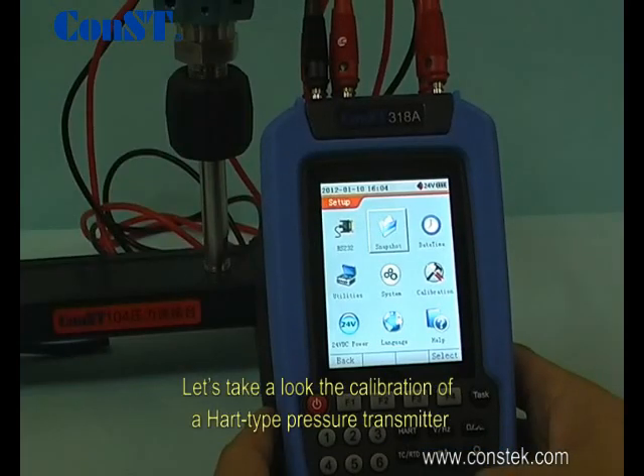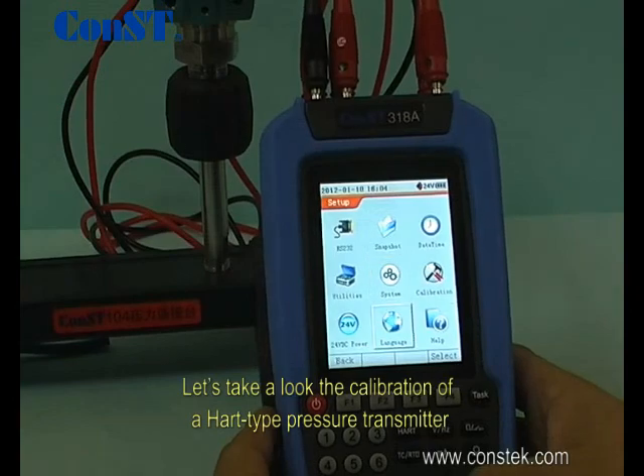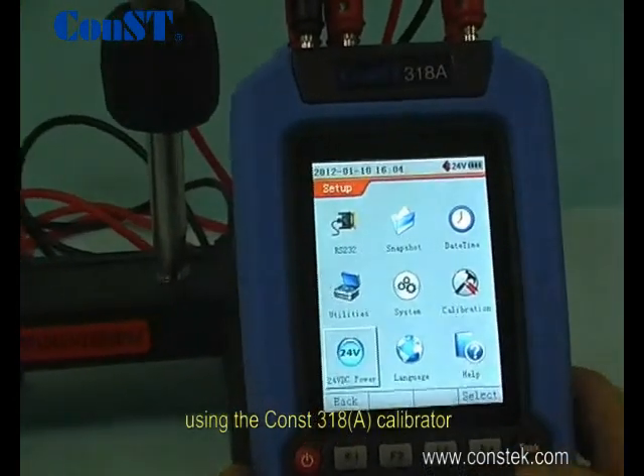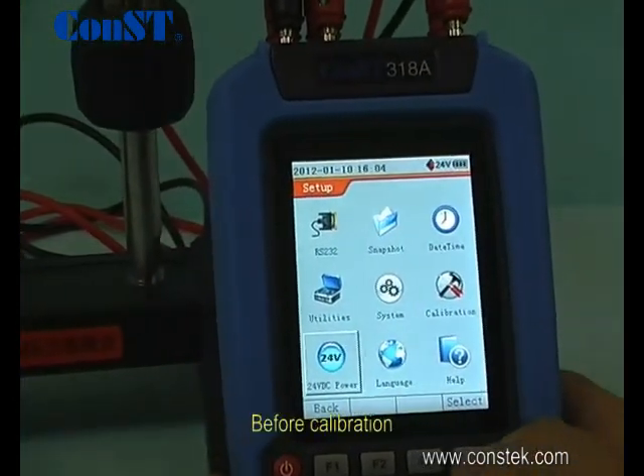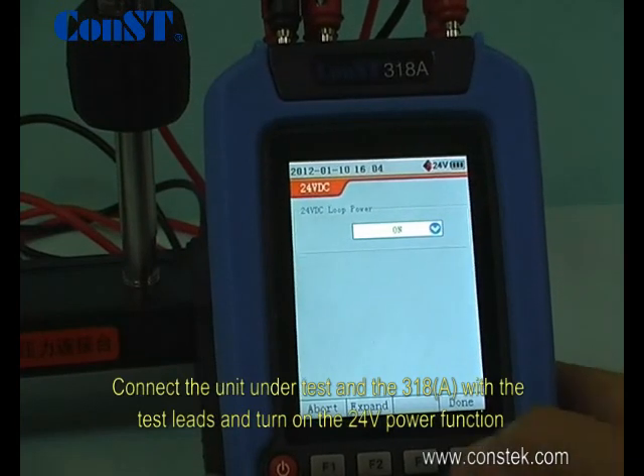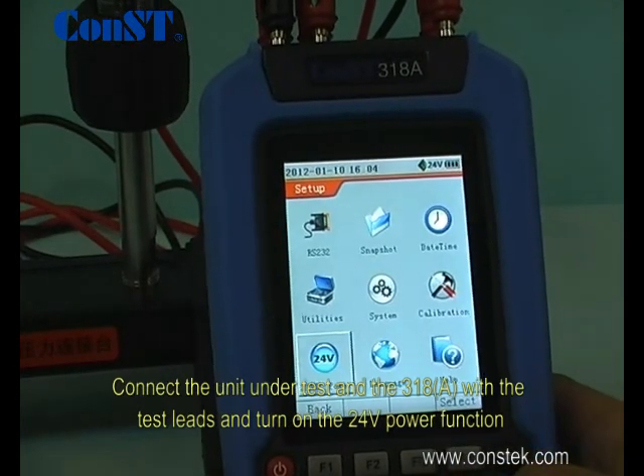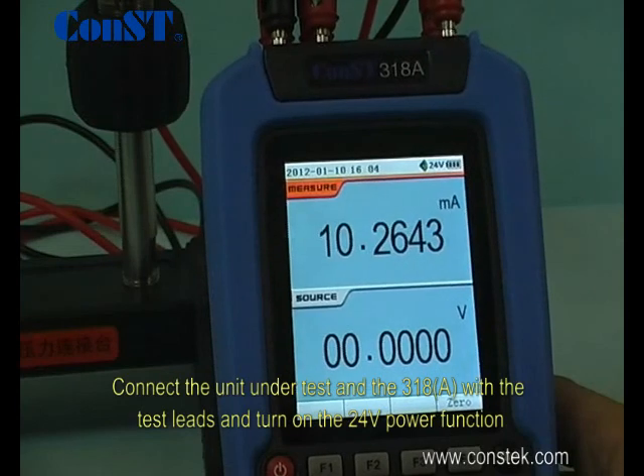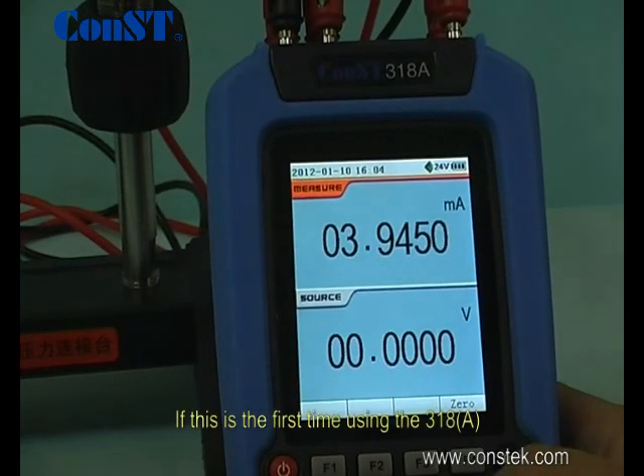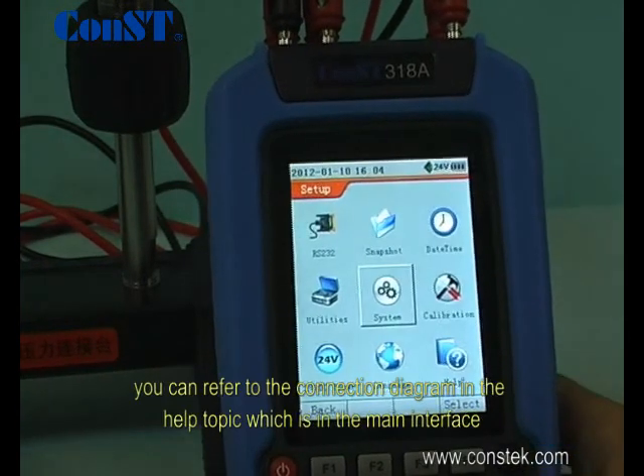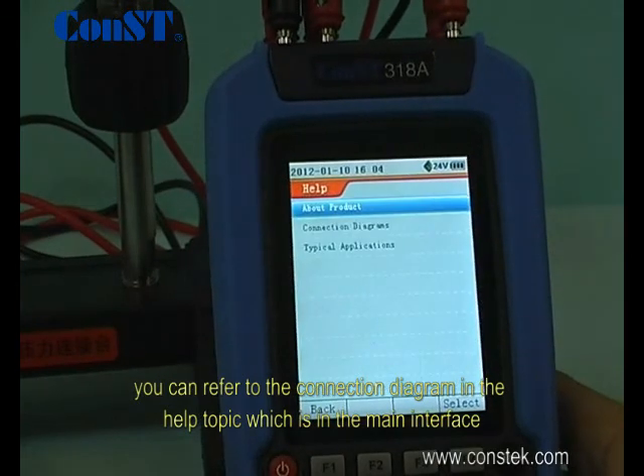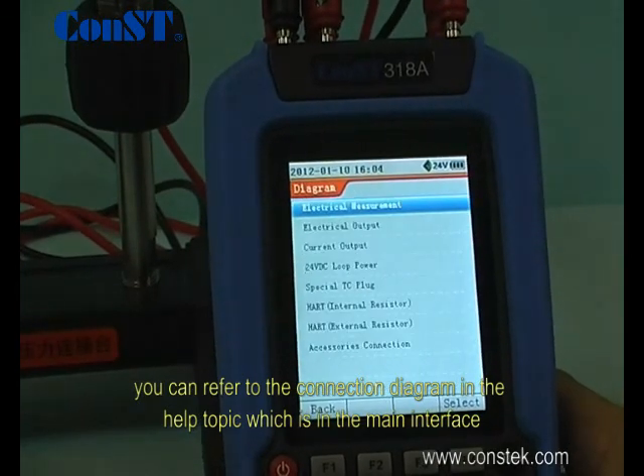Let's take a look at the calibration of a HART-type pressure transmitter using the ConST318 calibrator. Before calibration, connect the unit under test and the 318 with the test leads and turn on the 24-volt power function. If this is the first time using the 318, you can refer to the connection diagram in the Help topic, which is in the main interface.